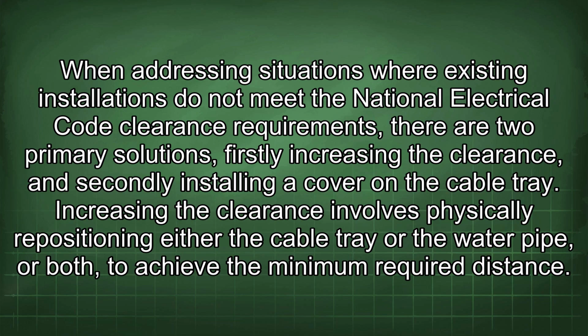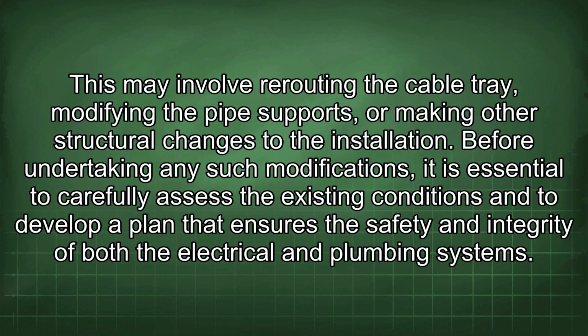Increasing the clearance involves physically repositioning either the cable tray or the water pipe, or both, to achieve the minimum required distance. This may involve rerouting the cable tray, modifying the pipe supports, or making other structural changes to the installation. Before undertaking any such modifications, it is essential to carefully assess the existing conditions and to develop a plan that ensures the safety and integrity of both the electrical and plumbing systems.